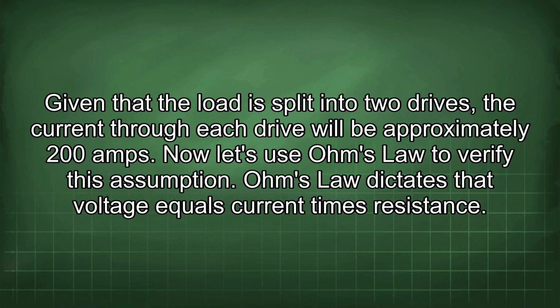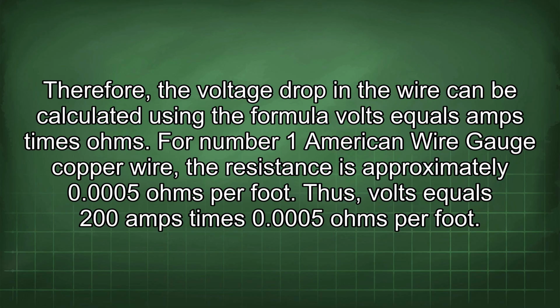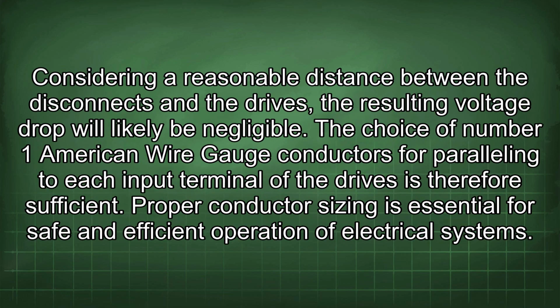Ohm's law dictates that voltage equals current times resistance. Therefore, the voltage drop in the wire can be calculated using the formula volts equals amps times ohms. For number 1 American wire gauge copper wire, the resistance is approximately 0.0005 ohms per foot. Thus, volts equals 200 amps times 0.0005 ohms per foot. Considering a reasonable distance between the disconnects and the drives, the resulting voltage drop will likely be negligible.